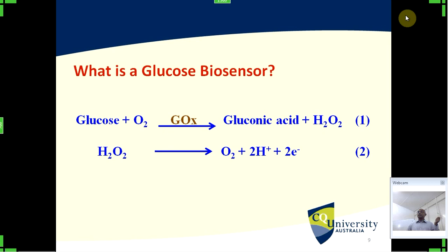handheld meter with a disposable sensor strip, this is the method we use. The amount of glucose in your blood - your blood always has oxygen, and every biomedical parameter has its linked enzyme, which converts that into a different product. When glucose and oxygen come into contact with glucose oxidase, the enzyme, it produces gluconic acid and hydrogen peroxide. This hydrogen peroxide, through an electrolysis process, you can separate into oxygen and two electrons. If we can collect these electrons and measure how many electrons are produced within a given time, then we can reverse calculate and give you the amount of glucose in your blood. That's the procedure happening behind the screen.